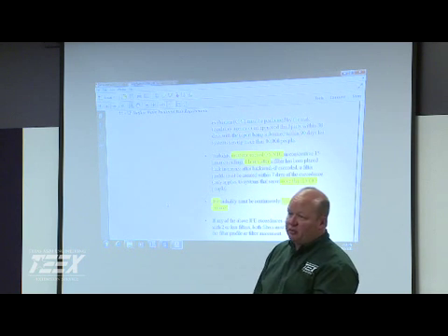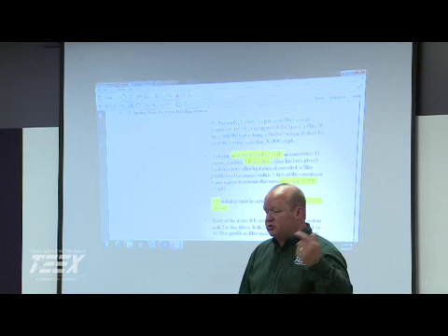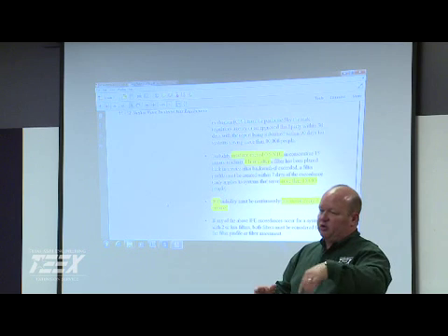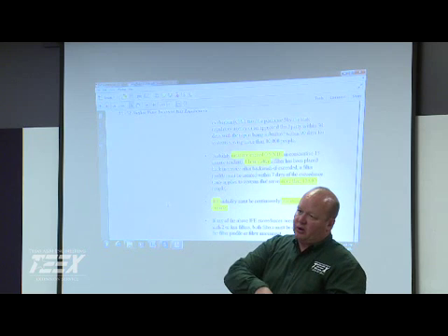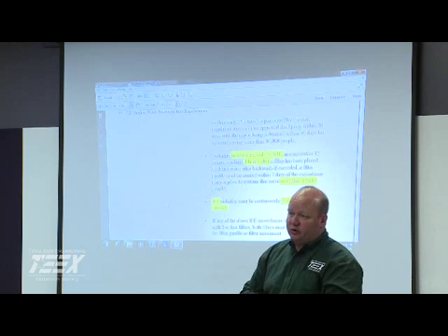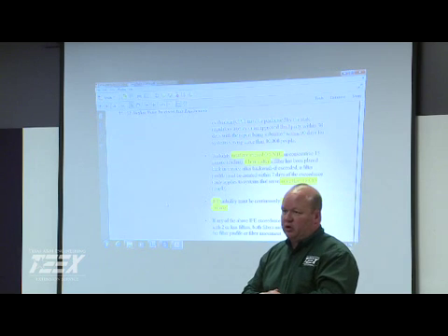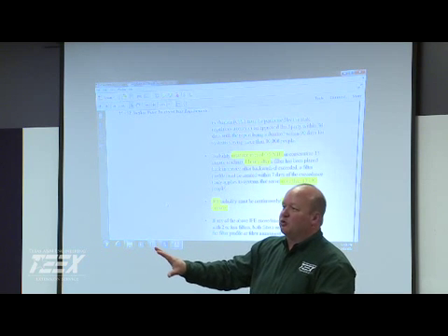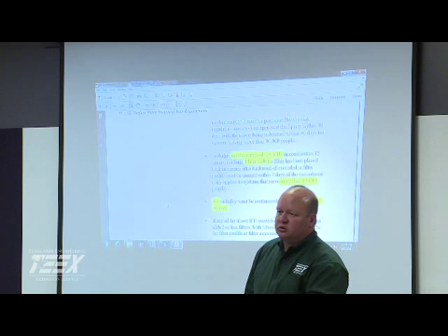If you got a filter that's having a problem, take it out of service. That's why it's good to have something on standby. Pull it out of service, you gotta backwash it again. And it also helps if after you backwash it and you do your filter to waste, you can let it sit for a while, it'll help compact it instead of putting it right back into service, because it's the greatest chance for you to have an exceedance unless you have a breakthrough on your filter. So if you're able to cycle your filters on and off like that and have something in standby, then that filter's gonna typically be better suited for your needs. What are y'all getting on runtime on your filters?